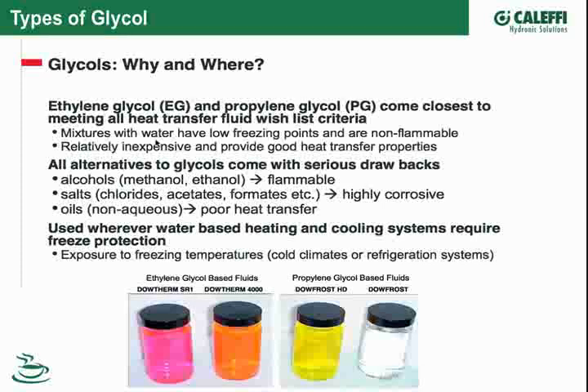Industrial-grade PG won't meet those specs, so it won't have the same low toxicity as food-grade PG. It really depends on what else is in there from a contaminant point of view. It's an excellent question because nobody really advertises what they actually have. A lot of people assume glycol is glycol and all propylene glycol is the same. Well, it's not. You need to be careful, and if you want a food-safe product, make sure you get that. Don't get hoodwinked into buying a product that doesn't meet your needs.